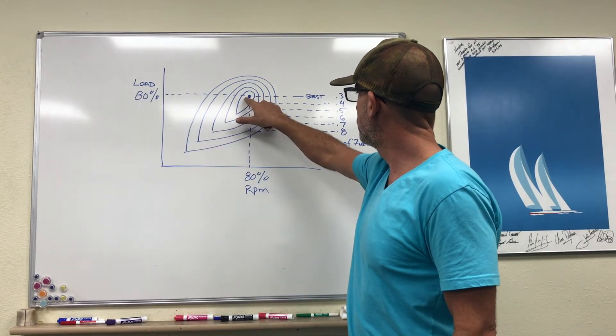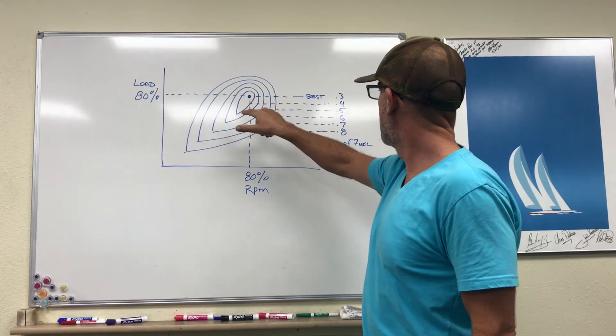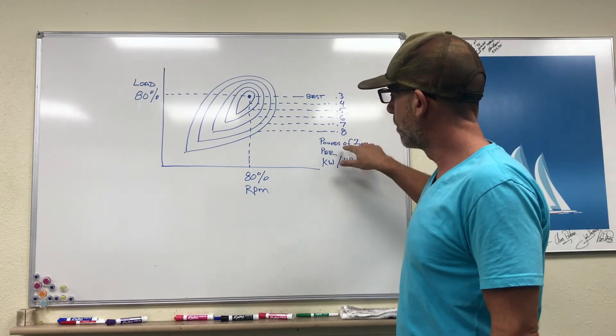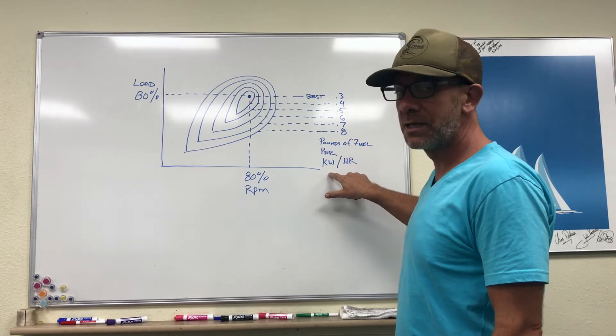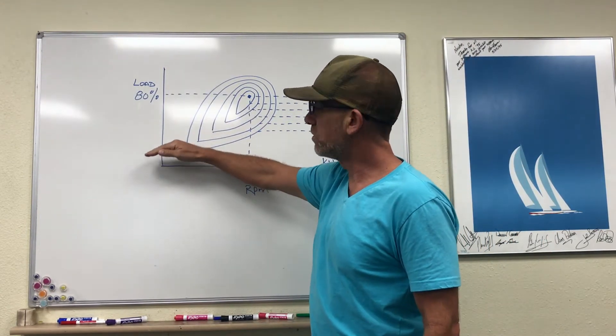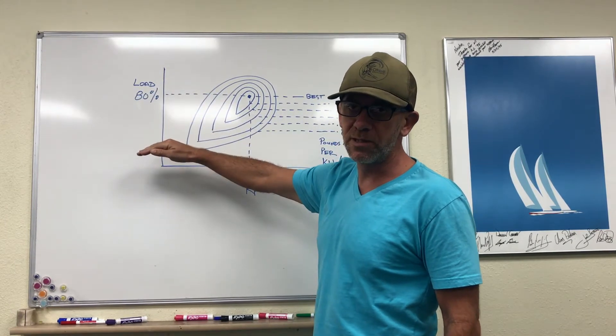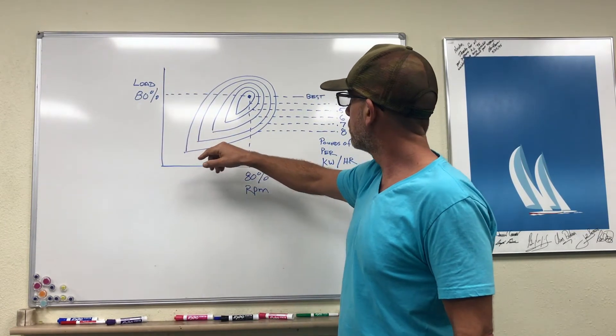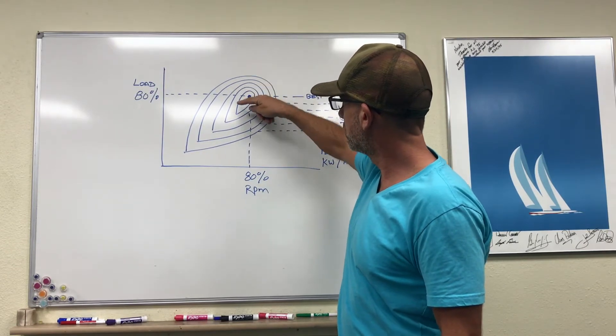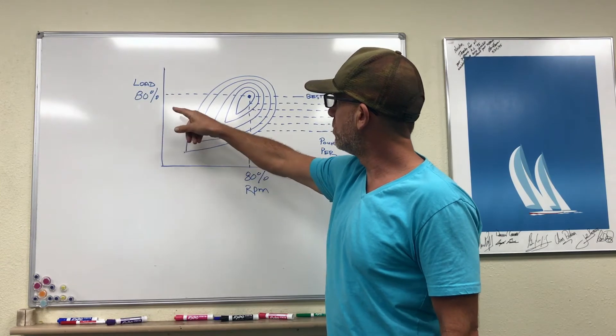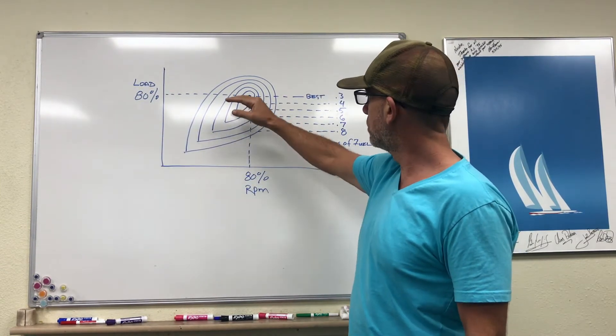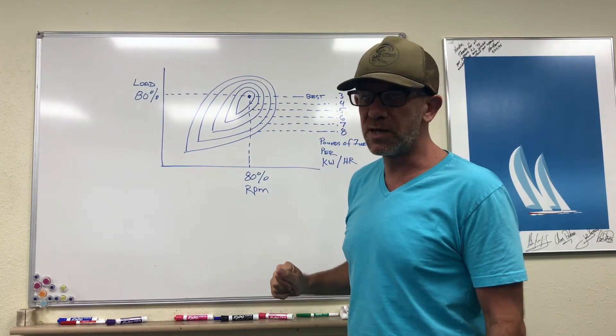...that is going to achieve your very best efficiency, and in this case this is 0.3 pounds of fuel per kilowatt hour. If the load changes, so the amount of power that you're drawing from the generator changes, you're going to move into these different concentric circles here. And depending how far away you move from that theoretical 80% load determines how your efficiency ends up.